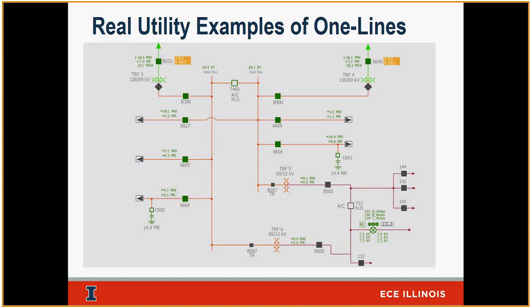This same substation also has a 12 kV line. Once the 69 is stepped down, it gets stepped down one more time from 69 to 12 kV, and you can see I have metering here. In real time, I see 8 megawatts going through down here to these feeders. There's that normal open point I talked about that ties two buses together. And then these are my feeders going out to the neighborhoods. We'll pick up next time, and I'll talk more about this device, which is a recloser, its measuring points, and all that kind of good stuff. We'll go through a couple more examples.